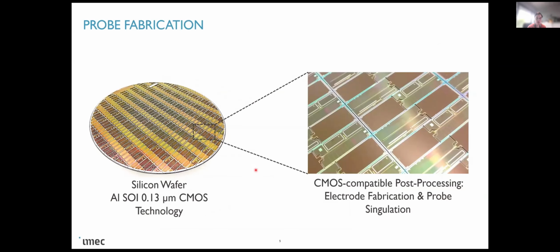And those goals are only possible by using a CMOS technology that enables us to integrate these electronics inside the probes. So the probes were designed by using this type of silicon wafer. The specific process is a 130 nanometer CMOS process technology. And we have the facilities at IMEC to develop a CMOS process or a CMOS compatible post-processing fabrication technique to do the electrode fabrication and also the probe singulation. So what is inside the probe are then all the active circuits that allow for the typical signal processing, such as amplification, the filtering, and the analog to digital conversion.